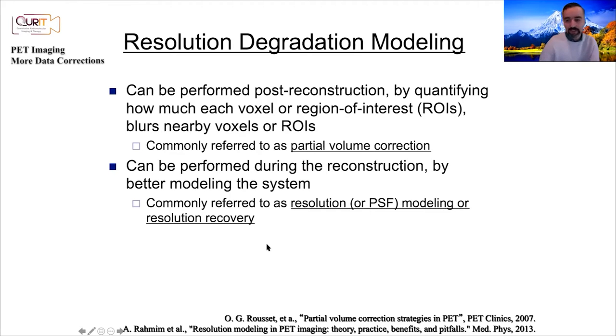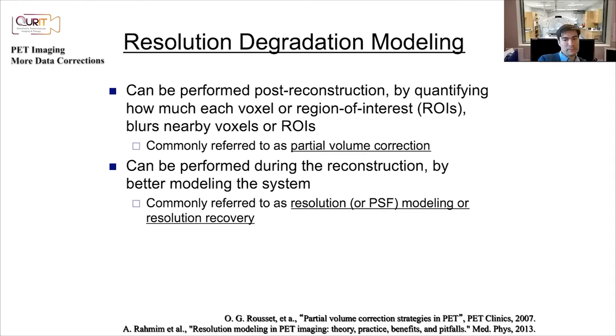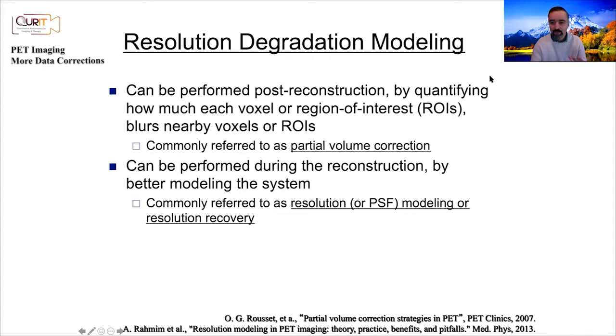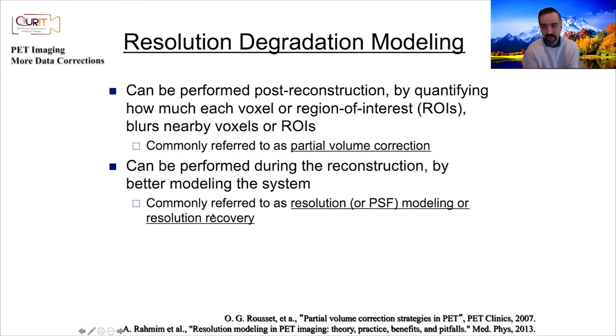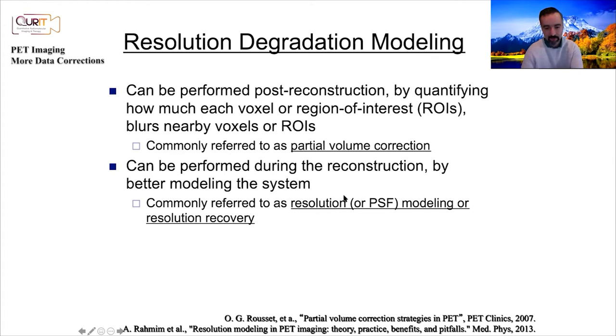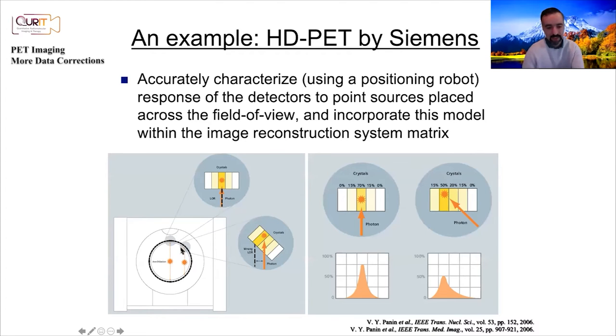For a long time these effects were not dealt with — they were considered facts of life. But people started thinking: why not model these phenomena within statistical iterative reconstruction? This is called resolution modeling, PSF modeling, or resolution recovery. In SPECT it addresses collimator-detector blurring; in PET it addresses detector blurring and other effects. If corrections are applied after reconstruction rather than within it, this tends to be called partial volume correction.